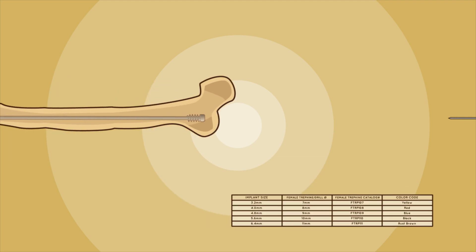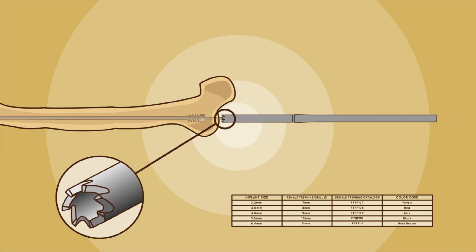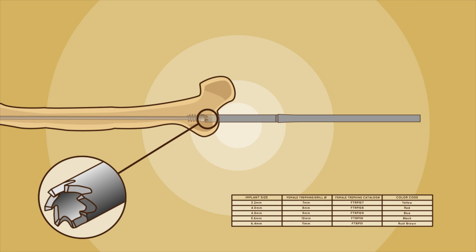First, advance a guide wire in the bone all the way in the cannulation of the female component to guide the female trephine. Then, the female trephine can be used manually or on power to clear a path for the female component.